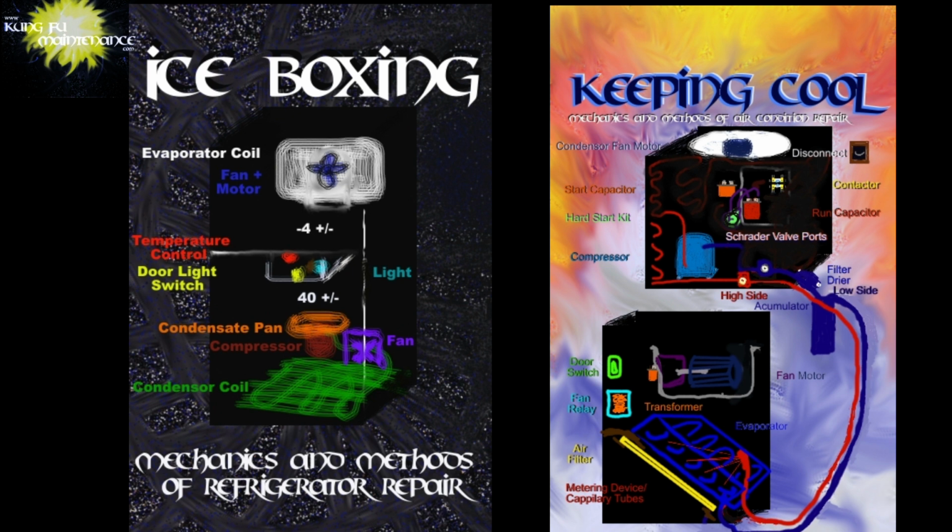Both systems have a door switch, but the function of the door switch is quite different. In a refrigerator, it generally only controls the light. For an air conditioner, it's usually a service door switch that shuts the whole system off if the door is removed, as a safety mechanism if a service tech is going to work on the system. Although a lot of service door switches wind up getting bypassed because sometimes they have problems. At least that's what I've seen a lot in the field.